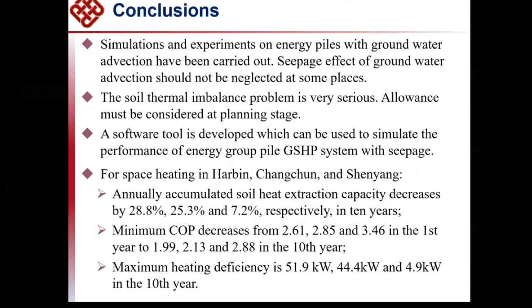And finally, I would like to give a conclusion. We have done simulation experiments of energy piles with groundwater advection. The seepage effect of groundwater advection must be considered, especially for some mountain areas. There must be water flow, even though the flow velocity is very, very small. The soil-thermal imbalance problem is very serious, so allowance must be considered at the planning stage. This is one of the main problems for the application of ground coupled heat pump systems in China.